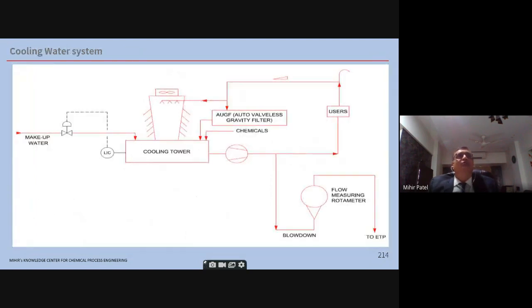Now the next is the cooling water system. A typical cooling tower is shown. There are many types of cooling towers depending on the capacity. Makeup water is shown here, level controlled on the basin of the cooling tower. The cooling tower pump is shown on the right. You have the users, and from the users, by gravity, the return water goes back into the cooling tower. I've also shown an auto valveless gravity filter, as you can see. That is nothing but an AVGF.